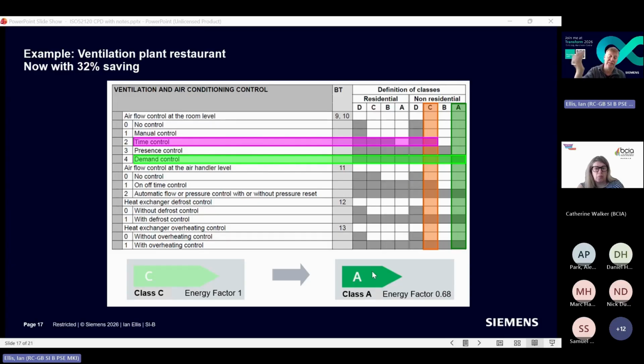And then if I do the proposed change I made, if I add that air quality sensor in there, I've now got demand-based control, so I can tell if the space is occupied or not and how many people are in there, and I can manage the ventilation system accordingly as a result of that data. Then I'm taking it to a Class A system. If you look down the bottom of this table, I've gone from Class C with an energy factor of 1 to a Class A system with an energy factor of 0.68 in this specific example. So my energy consumption is reduced by that amount.